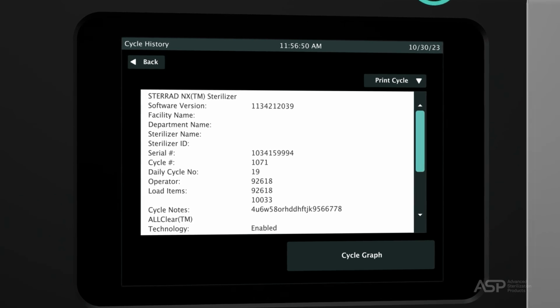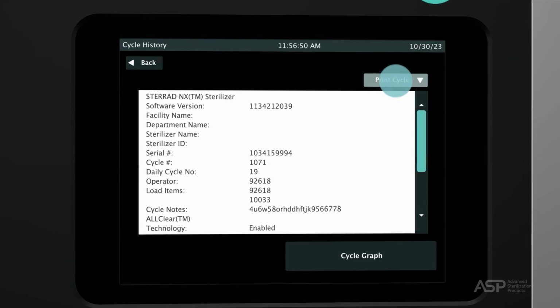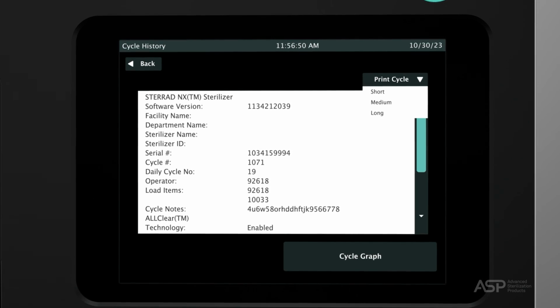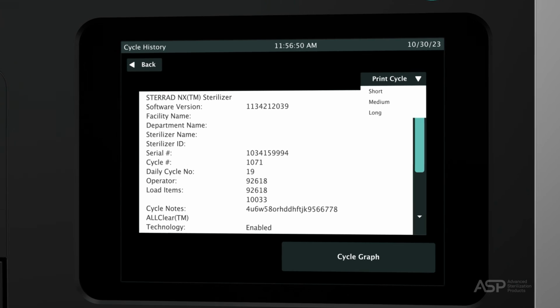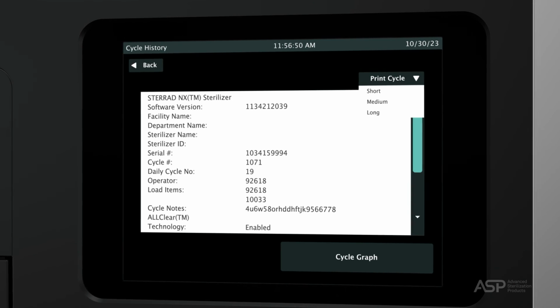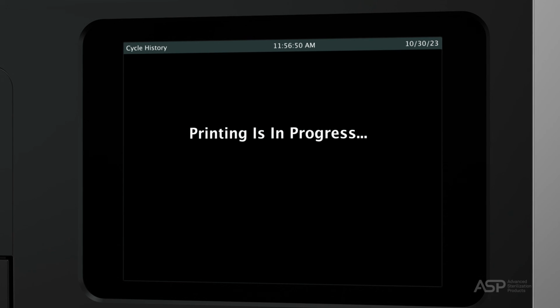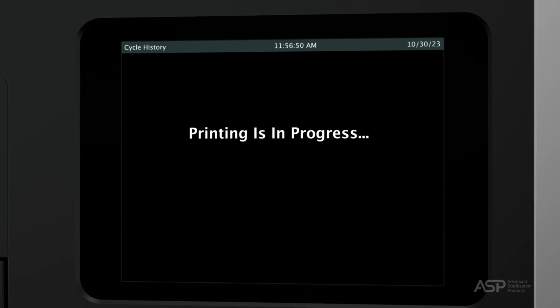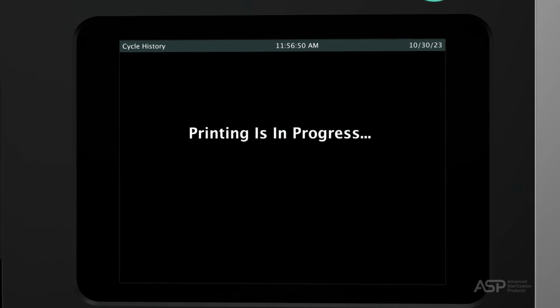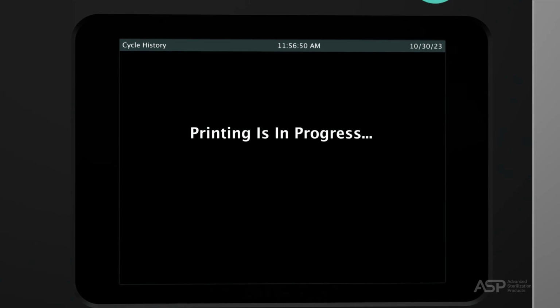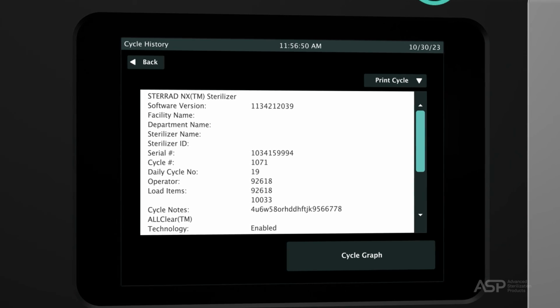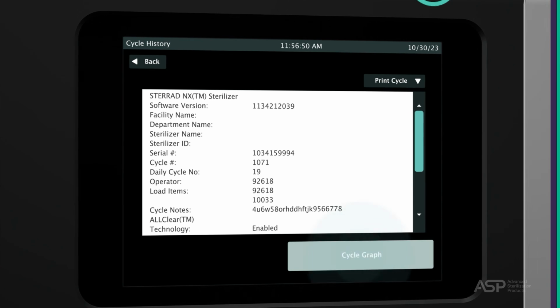Information is extracted from the cycle history file to produce the short format report, medium format report, and the long format report. The cycle history file contains information that is vital to a healthcare facility's record-keeping and traceability procedures. The sterilizer's memory holds data from the last 50 cycles.